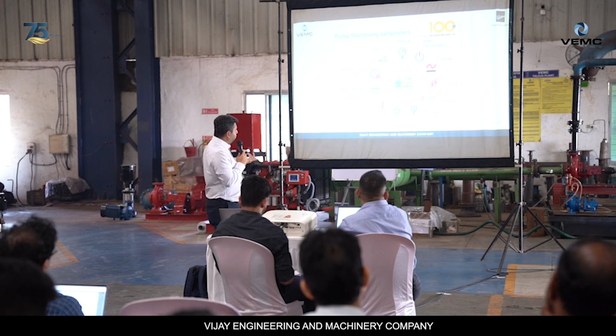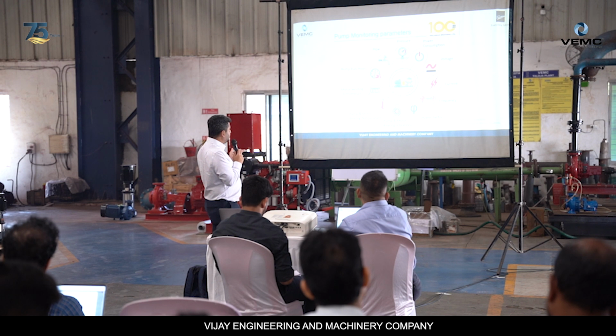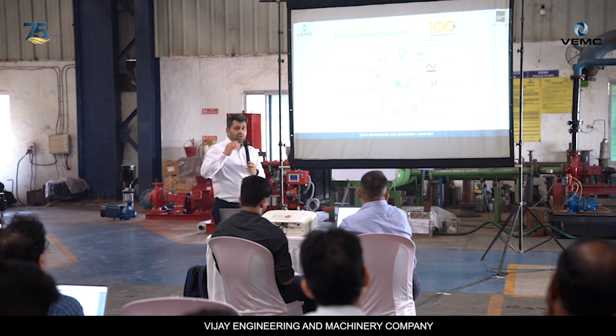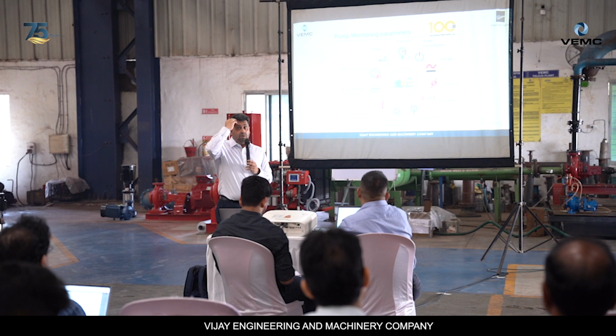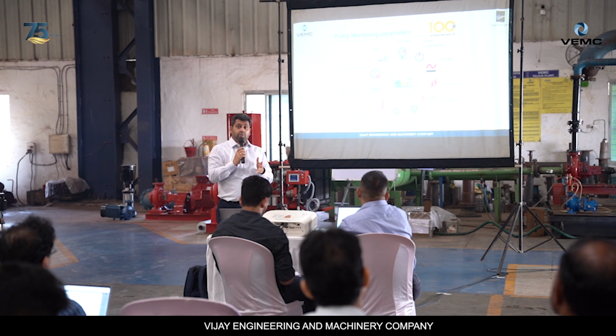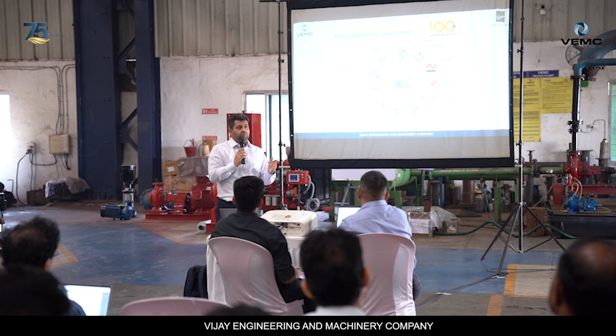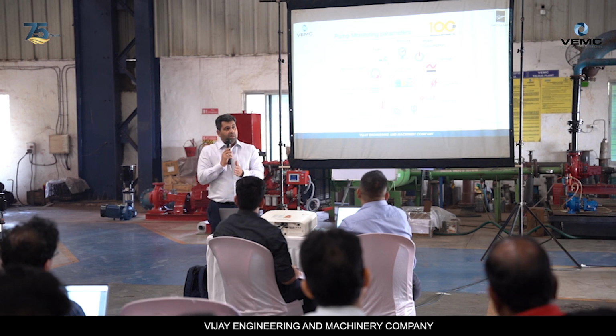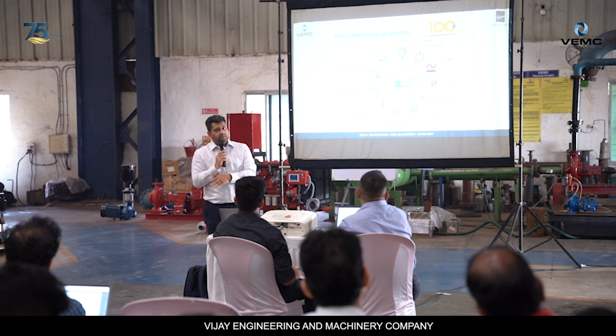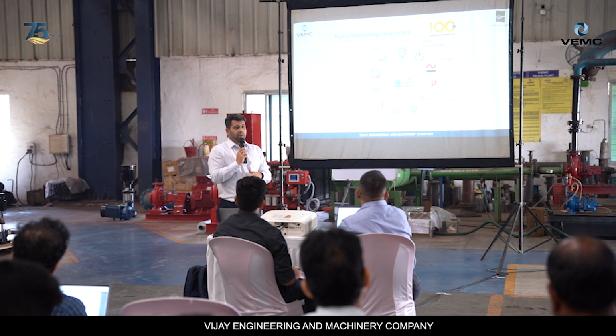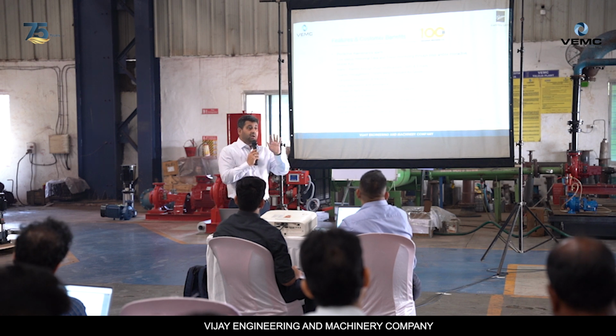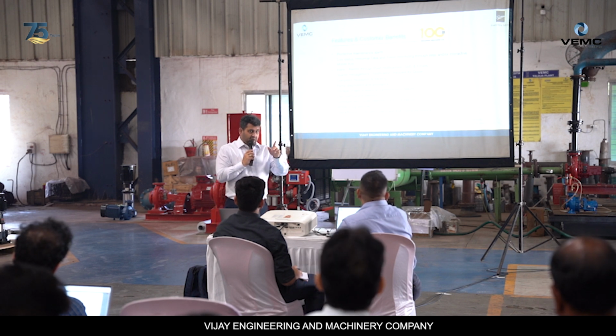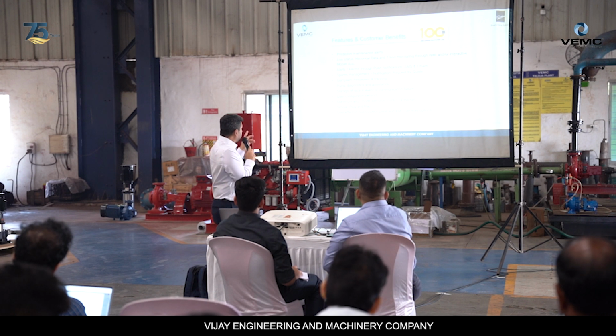Then we have pump and motor bearing temperatures - this becomes very frequent - and motor winding temperature. This is for continuous duty operations where your utility pumps are, so motor winding temperature becomes essentially very important. Currently we have IE2, we've moved to IE3, and going ahead we will move to IE4 in the future, where you'll have PMS motors, permanent magnet synchronous motors, coming into play.